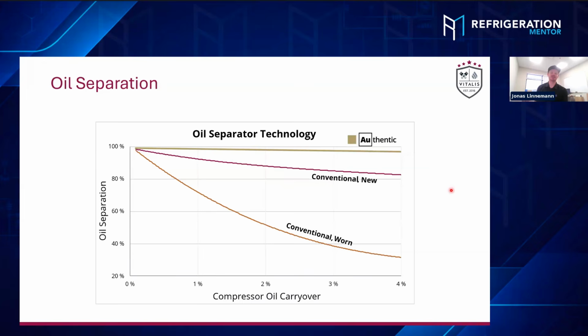This then leads to the effect that you lose just 2% of the total oil carryover into the system, and 98% stays right away in the oil reservoir. That ends up meaning you do not need to fill in another gallon or two into the system after the whole system is saturated, right? Yeah, because we want to make sure that we keep as much as possible at the rack, at the system, versus going out into the system. And this can happen in different ways. Like if you have bad valves on a compressor because of overheating or something, or rings, that could cause a higher carryover rate. You're just pumping out oil. So there are a lot of things that we need to look at, because I think that's one of the things that we'll talk about a little bit in troubleshooting oil.